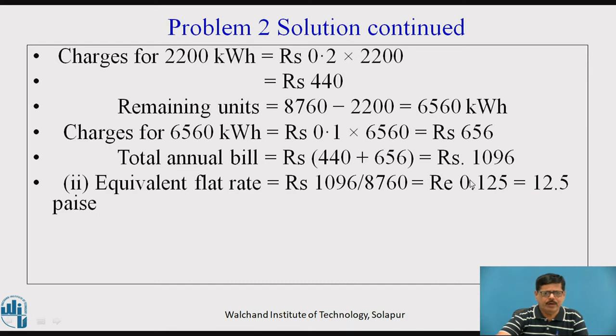The equivalent flat rate, if we want to calculate, will be equal to total annual bill divided by total number of units — so 1096 divided by 8760 — which comes out to be Rs. 0.125, that is 12.5 paise per unit.